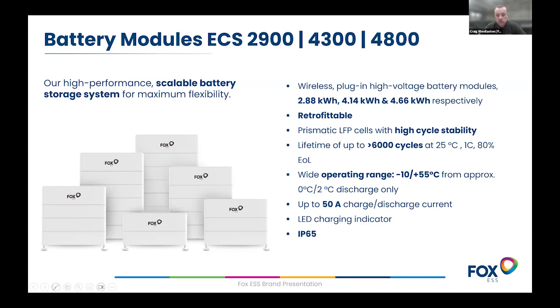In other words, the rate of charge and discharge is typically the maximum the inverter is capable of outputting. If we talk about the K series, the bigger single phase hybrid, 50 amp charge, so 4 batteries, 200 volts times your 50 amps is 10 kilowatts. So you can achieve 10 kilowatts of continuous charge and discharge. If you had 2 K series in parallel on a 20 kilowatt system, you could have that on each inverter, and you get 20 kilowatts. So you can see how that scales and how the rates of charge are very high.